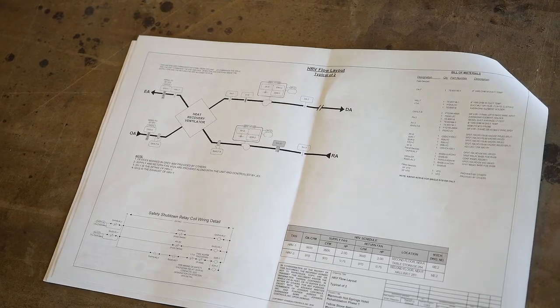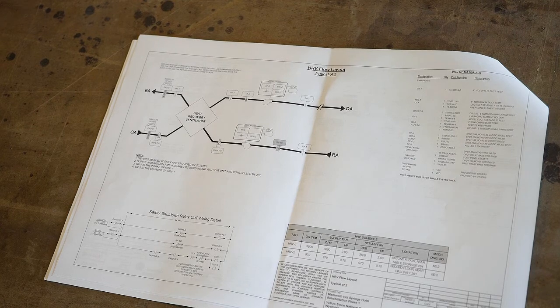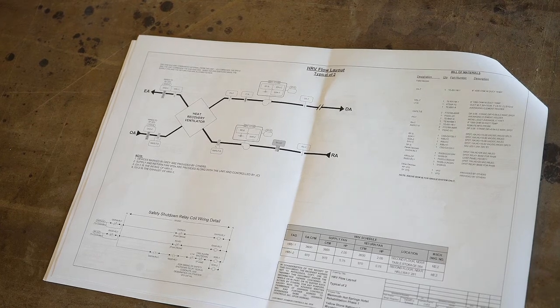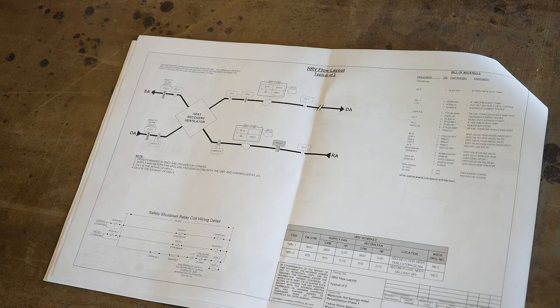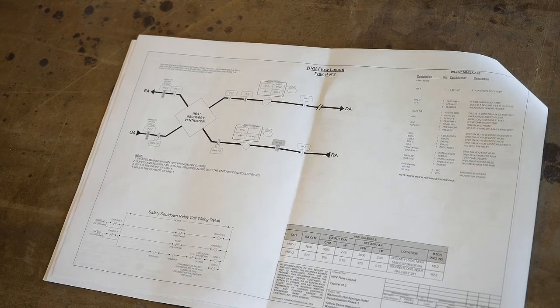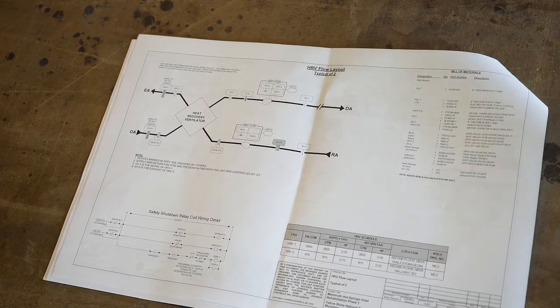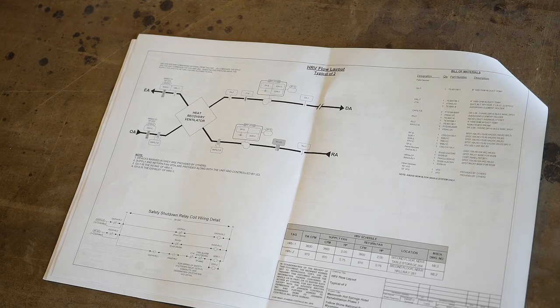So something to keep in mind on the HRV units: there is no heating and there is no cooling on them. They are strictly for fresh air from outside, bringing it into the building and exhausting air out. They're designed to take the heat that's in the air going out and temper the air coming back in.